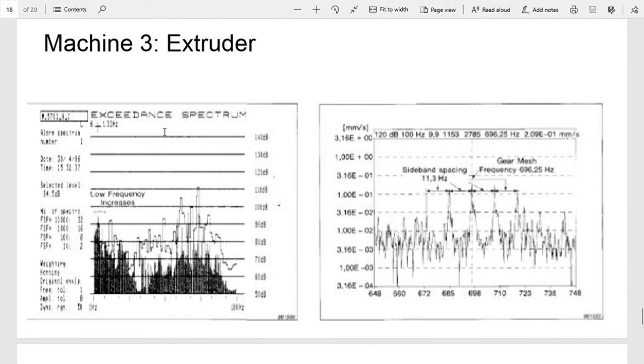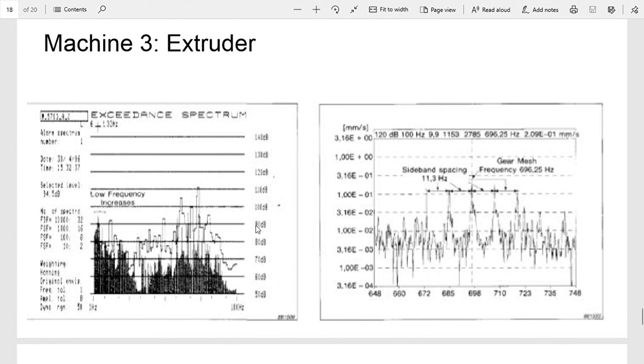The manufacturer of these extruders recommends that they be rebuilt after 250,000 running hours. But since they introduced the vibration monitoring, they found that in some cases this life has been extended almost by twice, up to 500,000 hours before a rebuild, so cost savings.